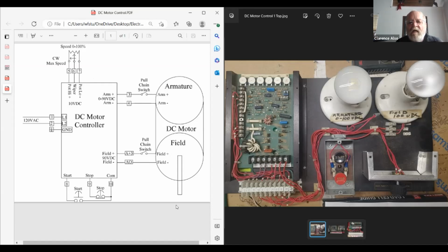Let's pick on Nathan again. So I press my start button, or before I even do that, my field is on, so that's good, I'm happy with that. Now I hit my start button and my armature light doesn't come on. I'm expecting something to come on because my speed pot is sitting at 50%. So I've got to check whether we started it up in the first place, or if the speed pot isn't working right or is set wrong. But we look at the knob and it's set right.